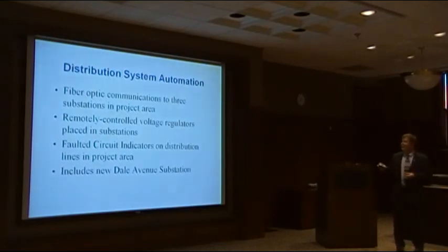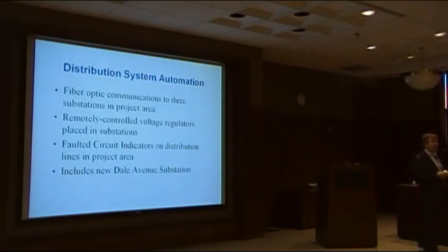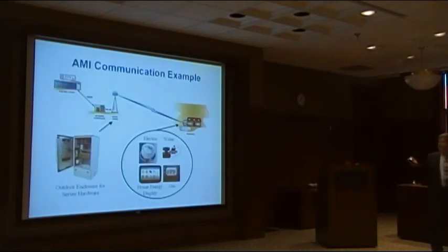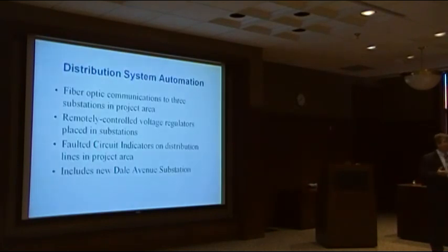We'll also be installing faulted circuit indicators on our distribution lines throughout the project area—about 240 will actually be installed. They will work basically the same technology as the meters, communicating via tower back to KUB, and through to KUB it would go to the outage management system. So again, our system operations folks will know where to go to fix the outage, and it gets customers back in service more quickly than is currently the case.